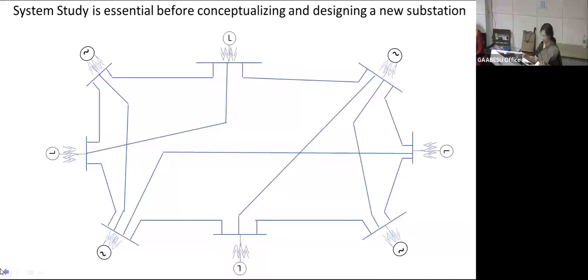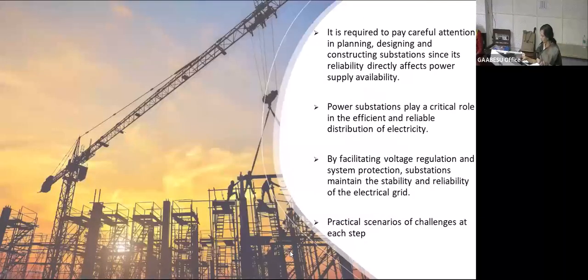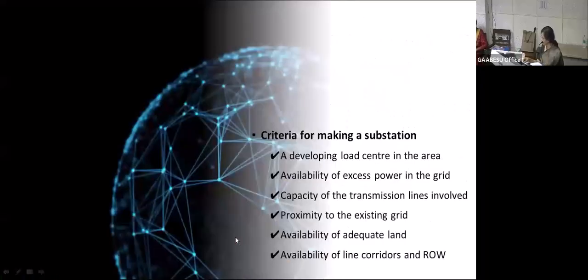So here we will consider an EHV/MV substation, that is, one having 220, 132 and 33 kV voltage levels. What are the criteria before starting our work? A developing load center has to be there in the nearby adjoining area. Availability of excess power has to be there, as discussed already. Capacity of the transmission lines and proximity to the grid. The lines have to pass through a nearby area where the land for the substation has been assigned. We have to connect to the existing grid.